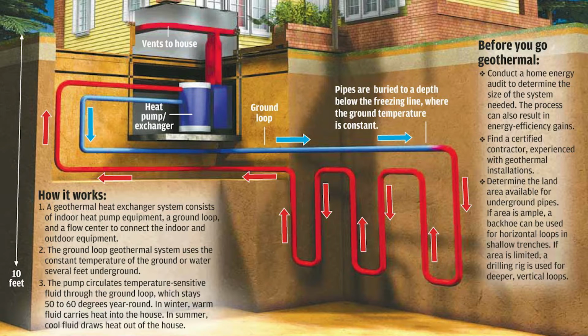A ground loop geothermal system uses the constant temperature of the ground or water several feet underground, usually 8 feet. The pump circulates temperature-sensitive fluid through the ground loop, which stays 50 to 60 degrees year round. So instead of exchanging air with the outside ambient, like we're going to do with the VRF, a geothermal unit has a more consistent temperature. Therefore you don't have as much environmental strain on the equipment, so the equipment life expectancy increases.